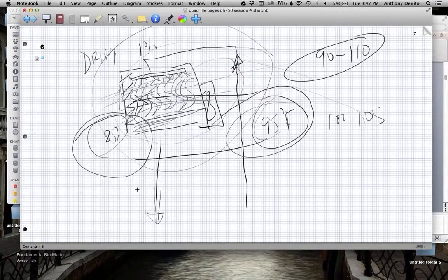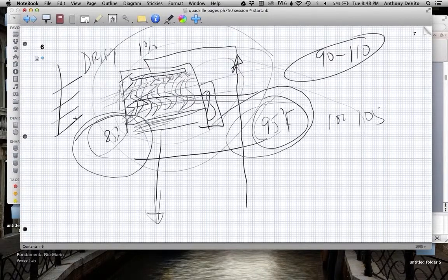But once you start to grow a lot of them, then you got to be concerned about that drift. And many of the outbreaks have occurred because these discharges from these cooling towers are right next to a fresh air intake to the building or windows to the building. It's not unheard of to find that happening. So it winds up getting pulled into the air conditioning system, and multiple people in the building get exposed.